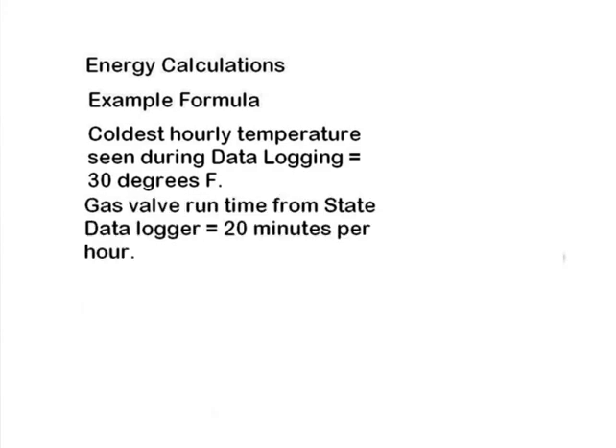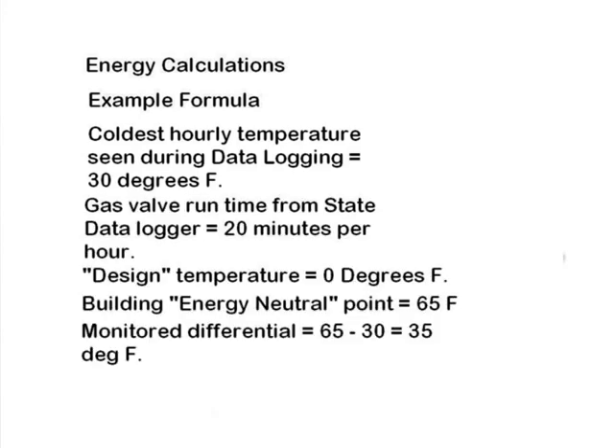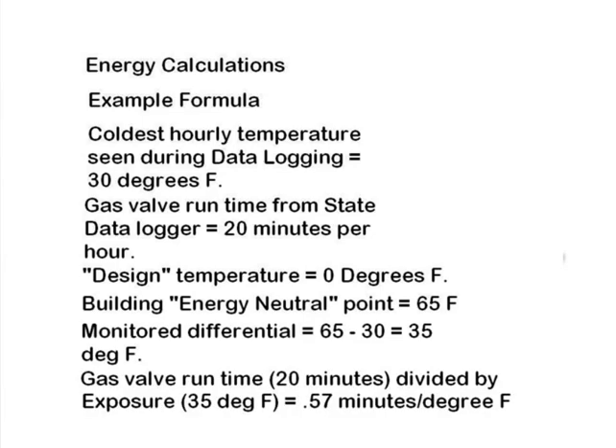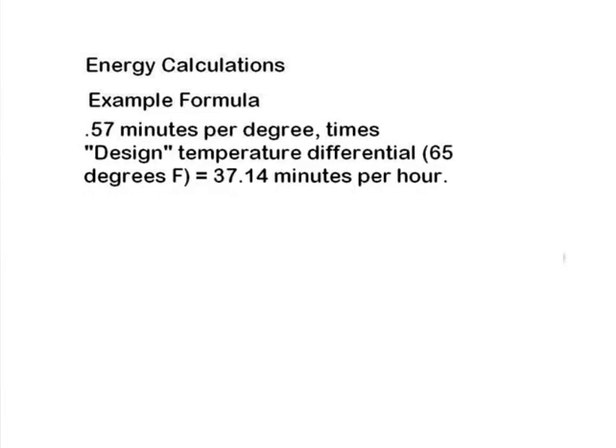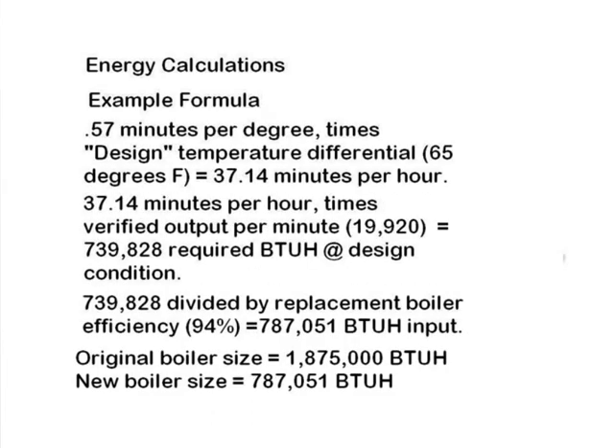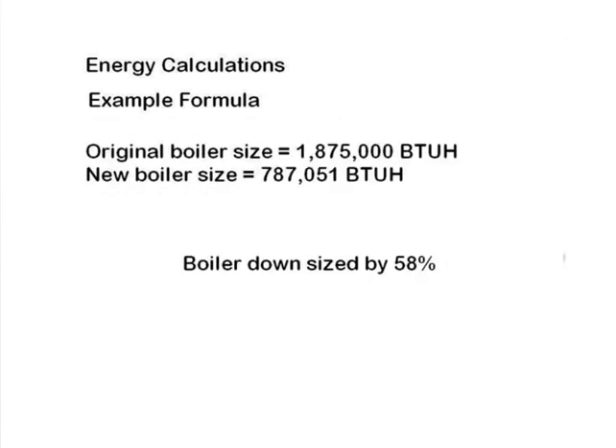Now that you have determined the net output of the boiler for a given period of heating demand, you can extrapolate this information to local design conditions and be relatively assured of having an appliance that will run considerably more efficiently due to proper sizing. As you can see, we've reduced the size of the boiler significantly — by a factor of 58%. This will result in a greater runtime fraction at design condition, less wear and tear from short cycling, and a substantial energy savings during operation.